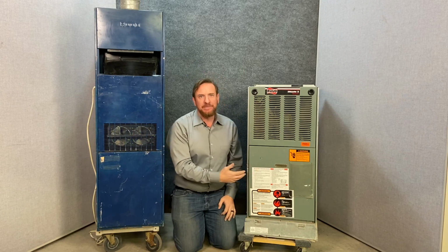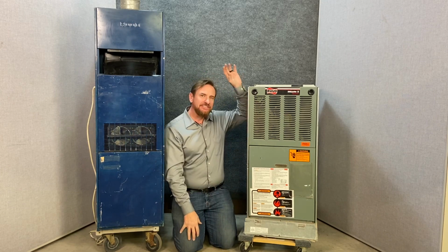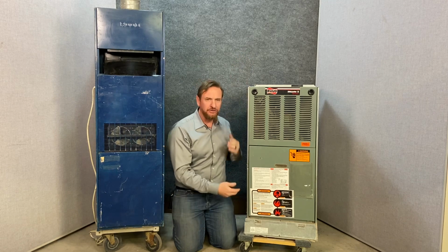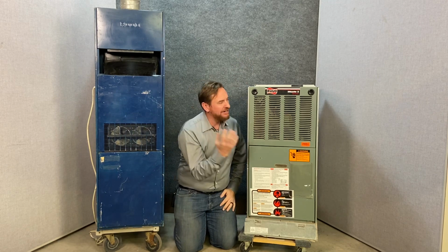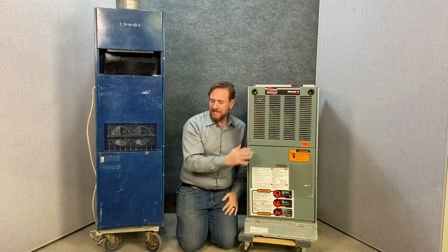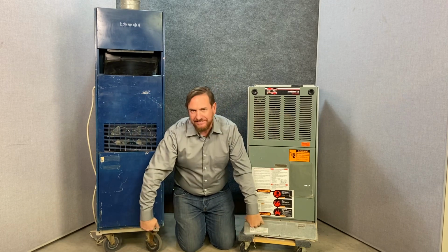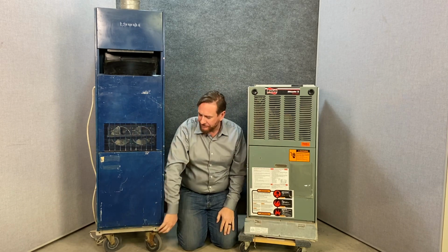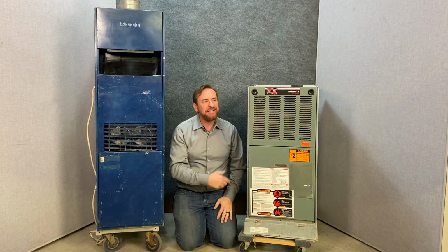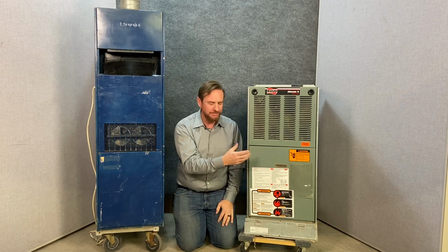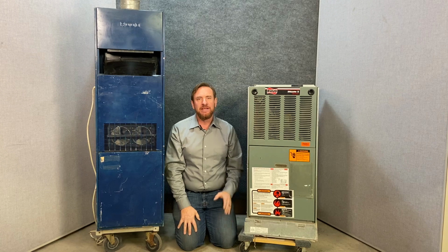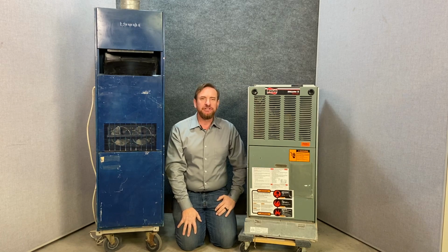This furnace has the same thing. Depending on the size of the furnace, the size of the hole, so many inches from the top, so many inches from the bottom of the platform, is the air of this closet for this to burn. The air from the house has to be sealed off. So this furnace would have to be sealed on the bottom so it's not mixing the combustion air, the air it needs to burn, with the air of the house. Now these upflow furnaces were also installed in basements.